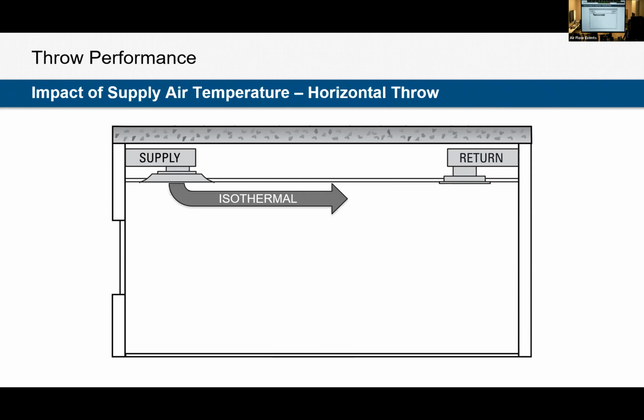Isothermal means that our supply air temperature is the same temperature as our space. There's no temperature difference between the supply air and the space. Almost never or very rarely are we supplying air into the space at the exact same temperature as the room. We're usually either actively cooling or actively heating. So we're either going to have 55-degree air in a 75-degree room, or it'll be 90-degree air in a 75-degree room. So if all of our catalog data is based on isothermal conditions, we're never actually performing there, what is going to be the result in our space?